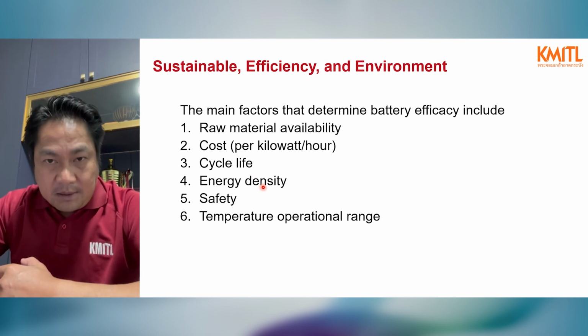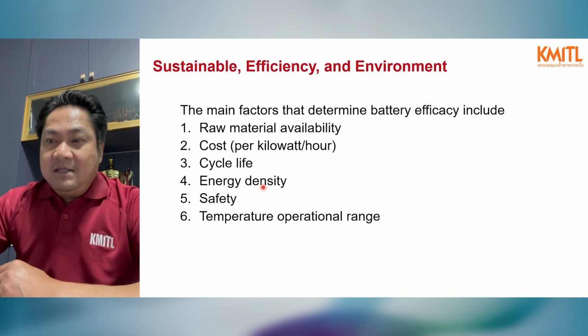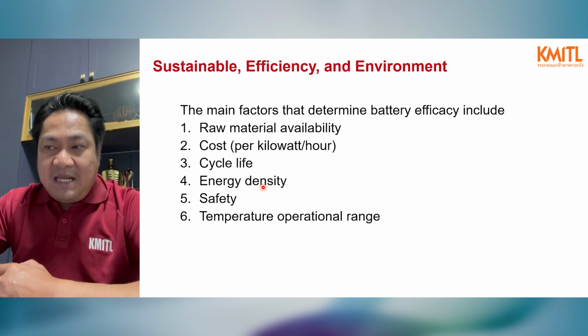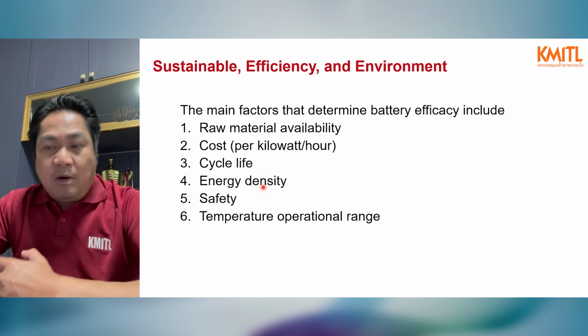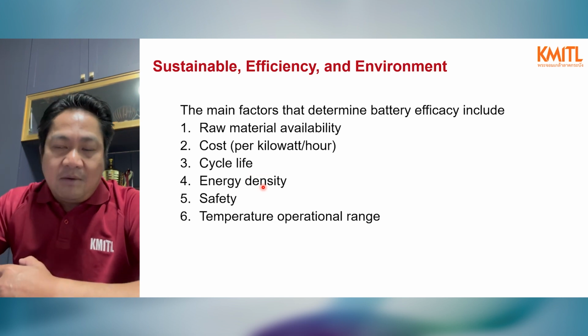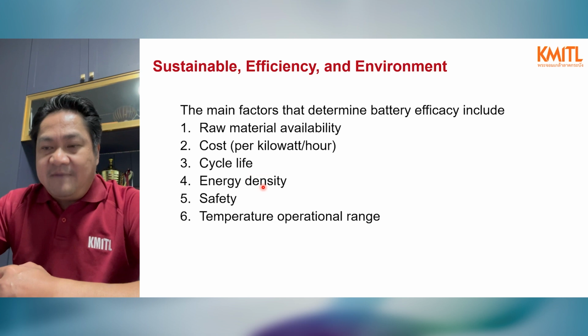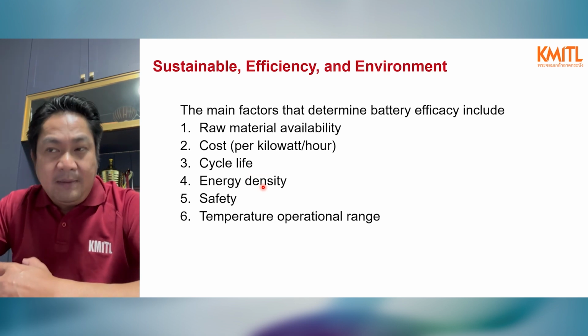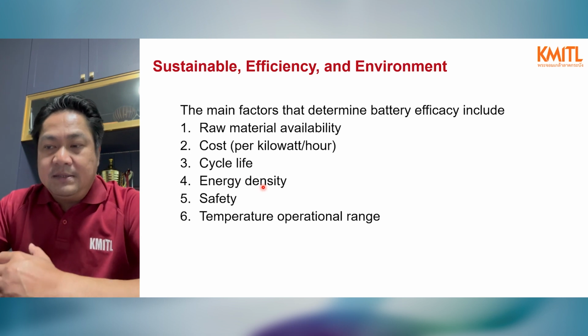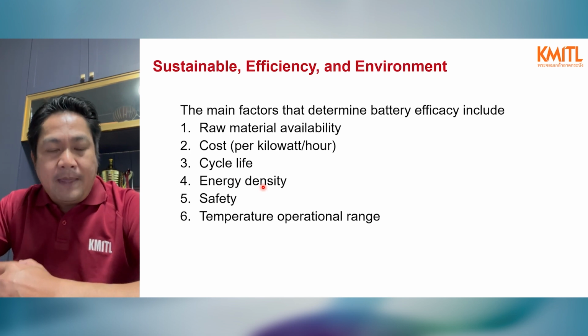Safety is also a main factor - as you know, when you get on a plane, they ask about power banks that aren't allowed, because they're flammable, which relates to safety of life. There's also the temperature operational range - lead acid batteries have limitations on their operating range. If the temperature increases, the lifetime of a lead acid battery will decrease by half.